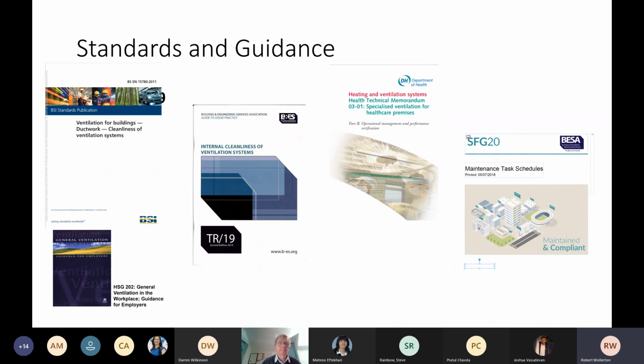We then later saw British Standard 15780 introduced in 2011. That was a standard which applies to both installation of new and existing ventilation systems. So we then went on to, and just at the bottom there, we've got HSG 202. That gives current ventilation standards and advises building managers on how to achieve effective ventilation in their workplace. It also outlines methods used to assess the effectiveness of the ventilation system and sets out legislation on what you are required to do to ensure effective ventilation.